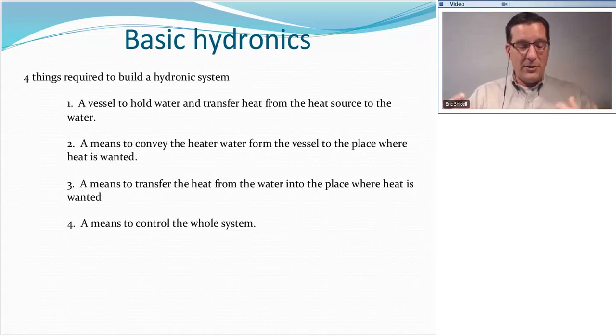And for those of you who don't have a whole lot of boiler experience, this can be a really big source of relief because you go, there's only four things to worry about. Now, of course, the devil's in the details, and those four things can manifest in many ways, but here's what they are. Number one, we need some kind of a vessel to hold the water and to transfer heat from the heat source into the water. Next, we need some way to move that heated water, and that should be a D right there. I just now realized that that's an R for all these years. We need to have some way to move that heated water from the vessel to the place where that heat is wanted. Next, we have to have some way to transfer that heat from the water into the actual place that heat is wanted, right? Like the room. And finally, we need to have some way to control the whole system.